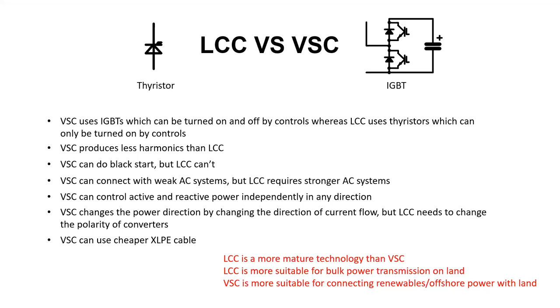However, having said all of this, LCC is a more mature technology than VSC. VSC is still emerging. LCC is more suitable, or at least considered suitable, for bulk power transmission over land because VSC is still emerging. With LCC, you would see across the world that DC voltages have gone up to 800 kV, whereas with VSC, the maximum DC voltage, I think, is 400 kV.